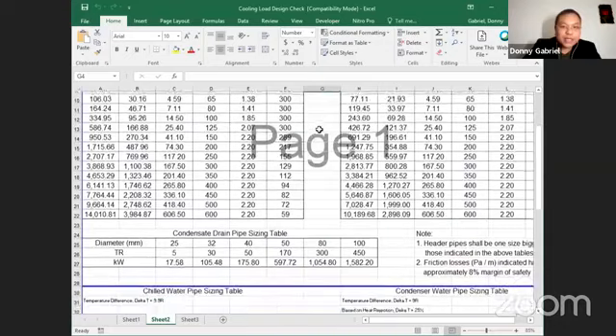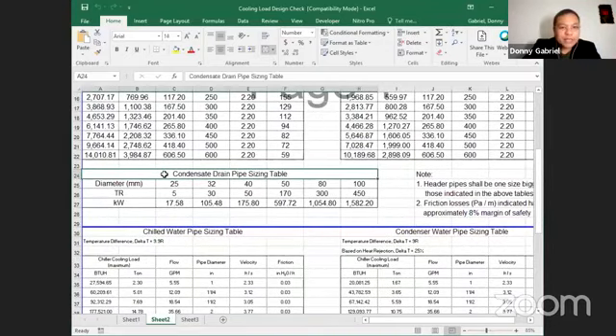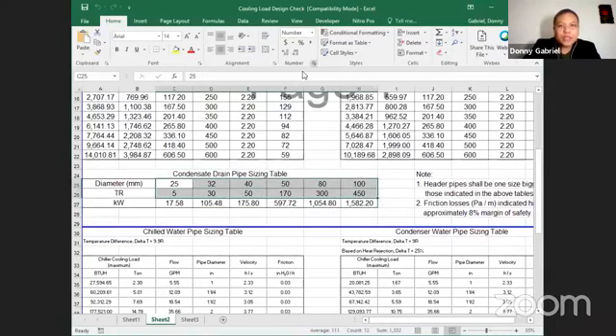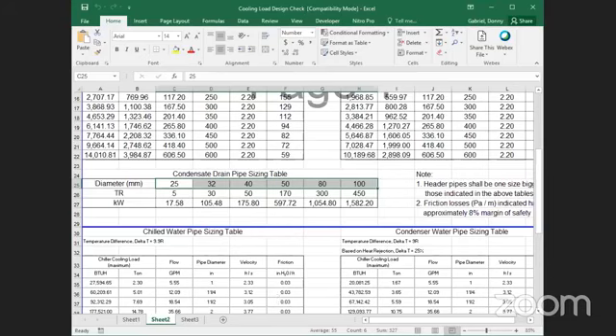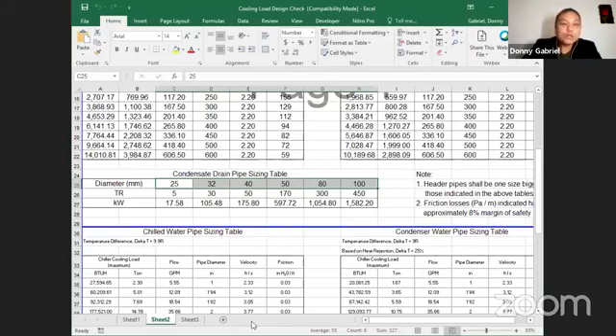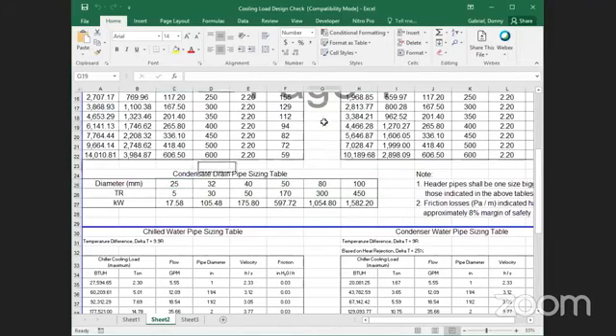So here, last time we discussed the chilled water pipe size. I think on the sizing table that I gave you, there's a condensate drain pipe sizing table. So based on the kilowatt, you will be able to get your pipe size diameter. Please take note of some local codes. Example here in Singapore, 25 mm or 1 inch is the minimum. I think in the Philippines, some of the aircon installers there are still using ½ inch or 15 mm. So check on your local codes what is the minimum pipe size required. All right. Thank you very much, Sir Eric. Any other questions that I can answer?